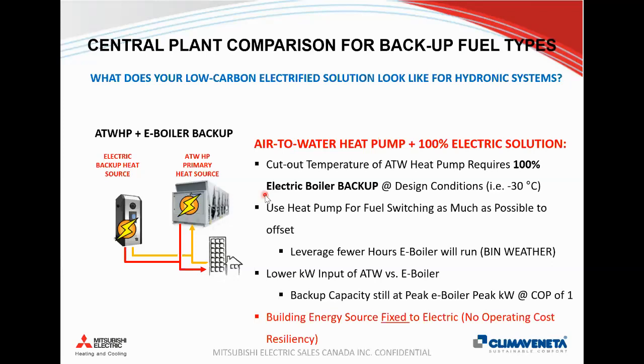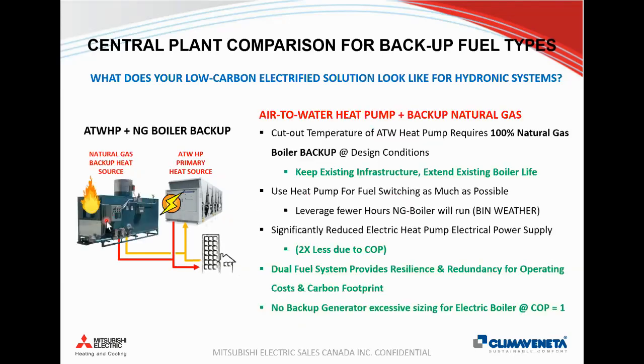But if your project requires that, we're going all electric now and we're going to make the investment now, that's great. You can certainly do that. You're going to leverage the heat pump, run that for a majority of the year, and use the backup electric boiler. But really, this is fixing your building to electricity from both your primary heat source and your supplemental electric boiler. So I think there's some advantages to be thought of for natural gas.